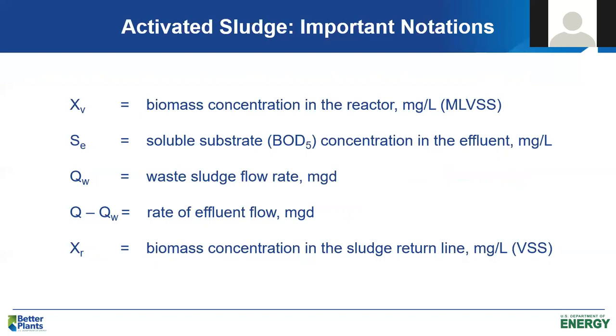And what we assume in our biokinetic relationship is that the influent biodegradable organic matter, the influent carbonaceous BOD5, is mostly in soluble form. Now, in actual practice, about 20 to 50% of the incoming biodegradable organic matter will be in solution, and 50 to 80% of it will be in particulate form. So generally, instead of using S0, which is the influent substrate concentration, the soluble portion, I'll generally use the total BOD5 of the influent.